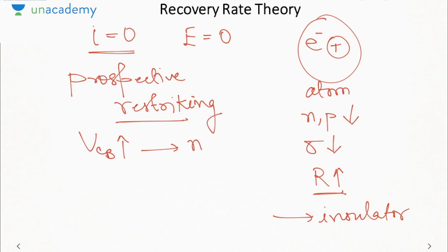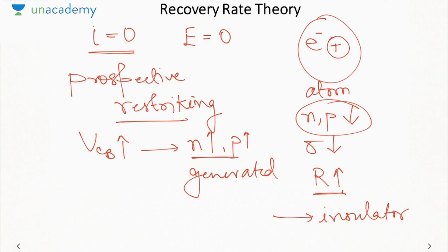Due to this restriking voltage, ions will be produced. So now there are two rates: one is the rate of recombination, and one is the rate of generation. If the generation rate is higher than the recombination rate, the number of ions increases and the arc will restrike or continue to exist. If the recombination rate is higher than the generation rate, the number of charge carriers reduces, conductivity reduces, and the arc extincts. This is called the recovery rate theory.